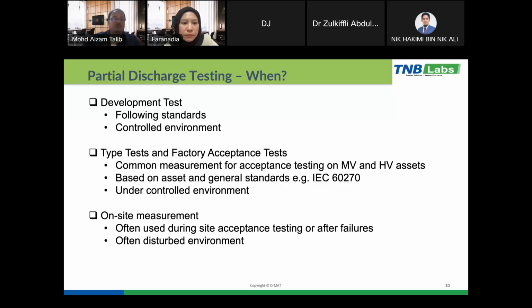Everything is controlled. And then the type test and factory acceptance test are normally done in the factory. This is the common measurement for the acceptance test on medium voltage and high voltage assets, transformer, cable, switchgear. And normally we follow the standard based on IEC 60270. And this measurement is also normally performed under a controlled environment. We perform it in a shielded room.